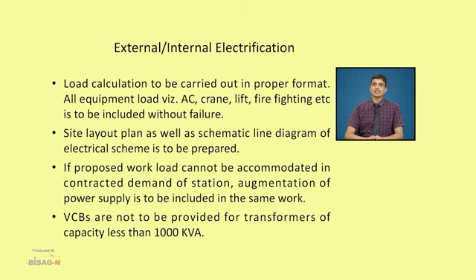Now I will discuss specific points related to external and internal electrification. Load calculation to be carried out in proper format. All equipment load, that is AC, crane, lift, firefighting, etc., is to be included without failure. Site layout plan as well as schematic line diagram of electrical scheme is to be prepared. If proposed workload cannot be accommodated in contract demand of station, augmentation of power supply is to be included in the same work. VCBs are not to be provided for transformer of capacity less than 1000 kVA.